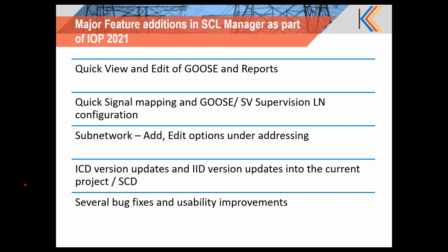There were several features added in SCL Manager as part of the interoperability workshop preparation. We changed the view and edit options of GOOSE and reports. We are also supporting GGIO signal mapping and GOOSE and SV supervision LN configurations. Previously, we had a different workflow to do that. We also added the feature to exclusively add and edit subnetworks under addressing. Then the other major feature addition was to support newer versions of ICDs in the project, and also import IID after the engineering.